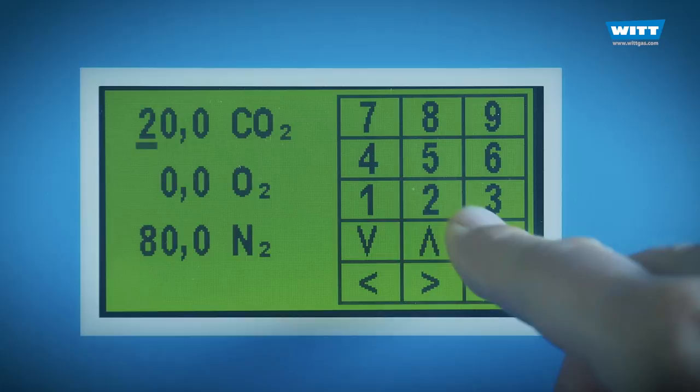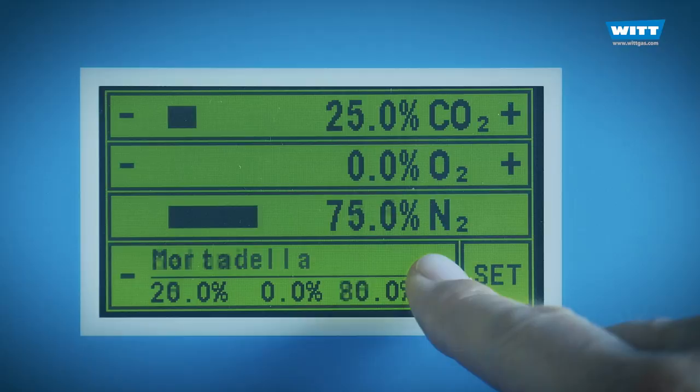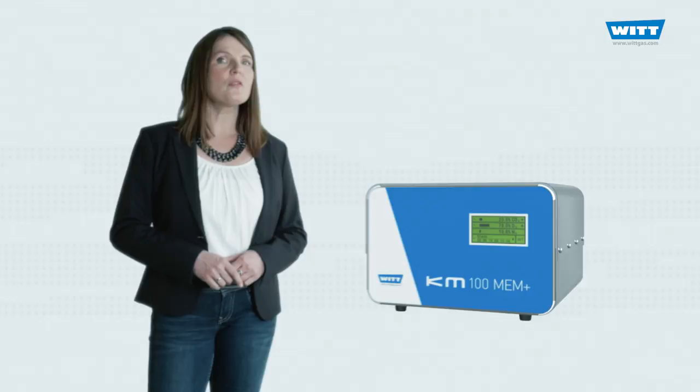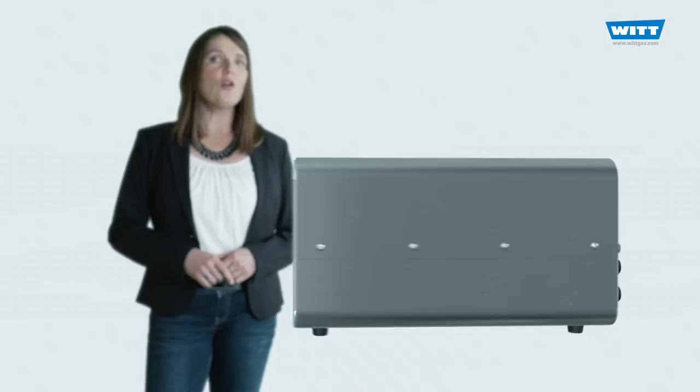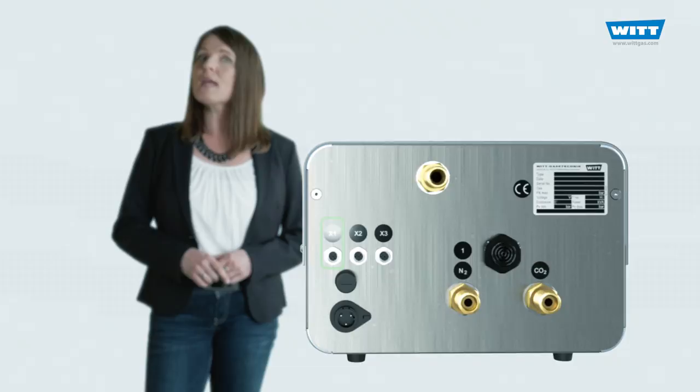The gas mixture setting couldn't be easier. You can also pre-define various mixtures and call these up at the push of a button. You can control the mixer via either the optional touch screen or via the analog 4 to 20 mA interface. The KM 100 MEM+ has a serial interface too, meaning it can be controlled centrally via PLC or PC.